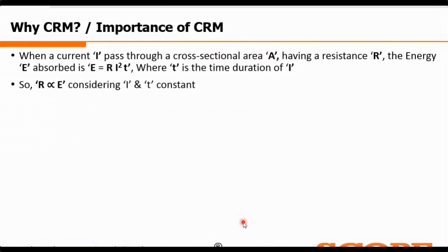Generally, we know that for healthy circuit breakers, the contact resistance is very low, for example around 40 to 50 micro ohm at least. But due to that fault, after the rated current passes through the circuit breaker, the I square R loss starts to happen.